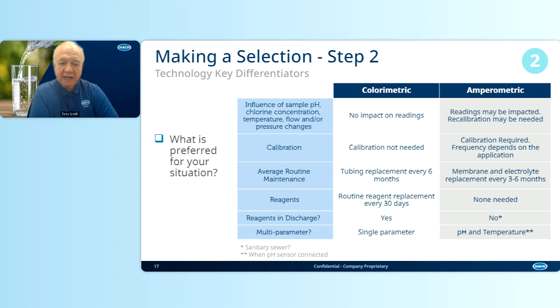So, average routine maintenance. With colorimetric, we're going to replace tubing every 6 months. With amperometric, we're going to have to replace the membrane and/or electrolyte every 3 to 6 months. That will cause you to have up to 8 to 12 hours of uncalibrated readings. It takes a while for the new probe, new membrane, to repolarize, stabilize, and get ready to go, so that we can actually do the calibration.